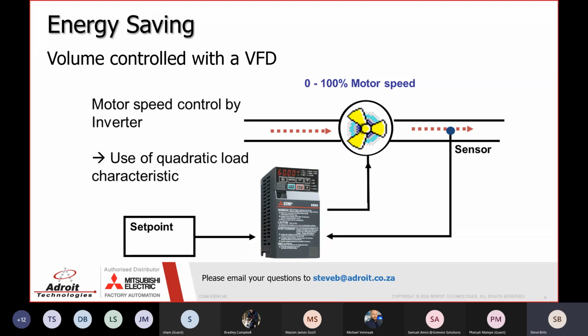When you install a VFD, you won't have any dampers or valves required, as you can use the VFD to control the flow required. And I've made a nice picture to illustrate the application. So we have our liquid or our air coming in. With the inverter, we can control the motor speed. We can take a sensor to measure whether we want to work according to pressure or to flow, and we set up a set point in the VFD to always keep at your required pressure or your required flow.